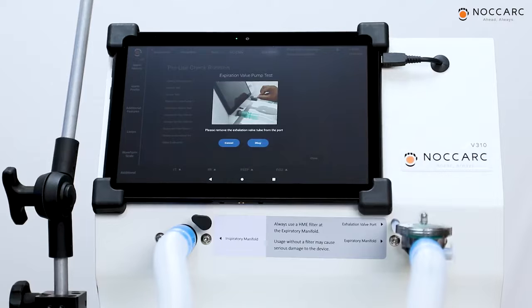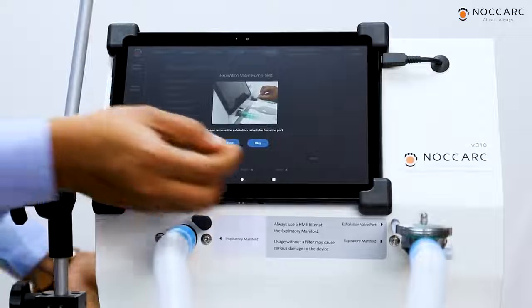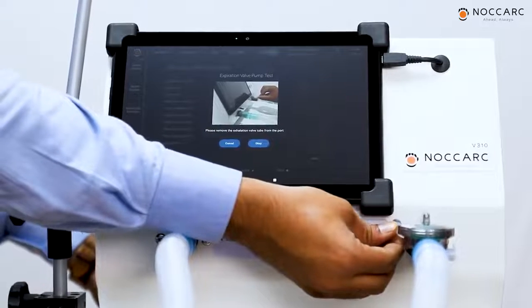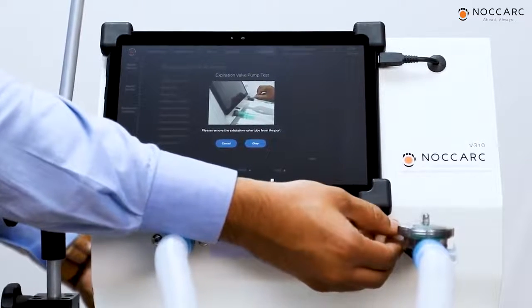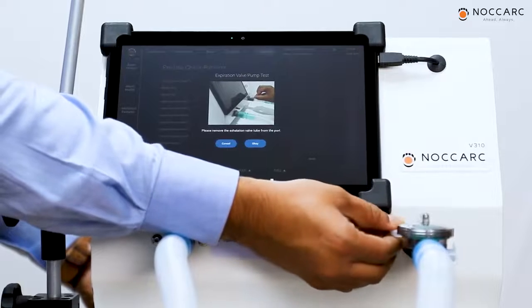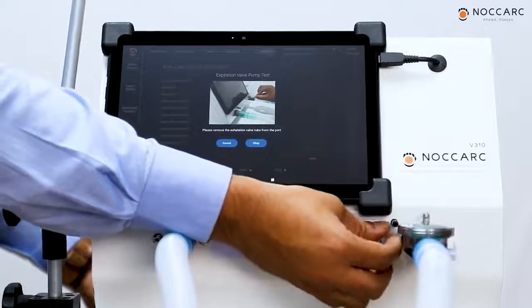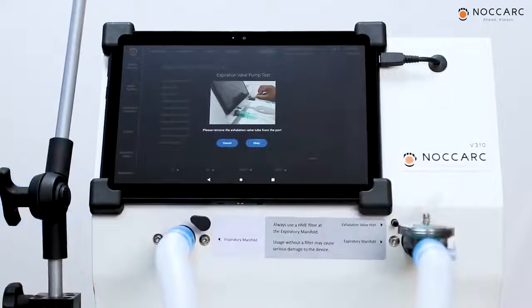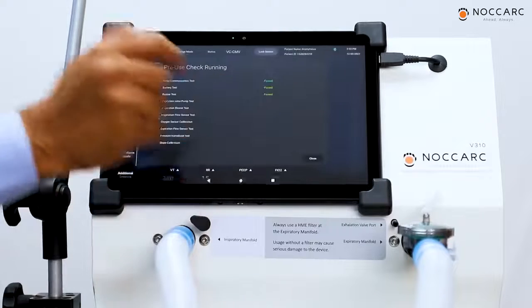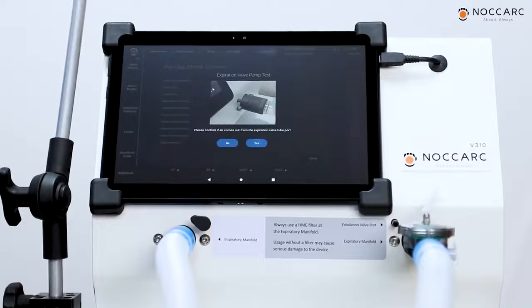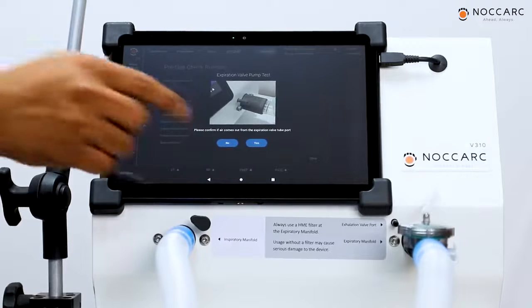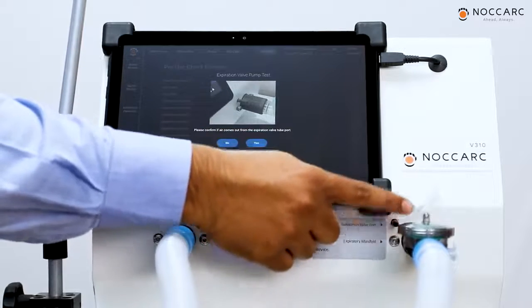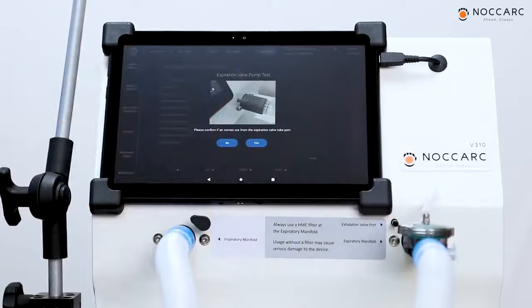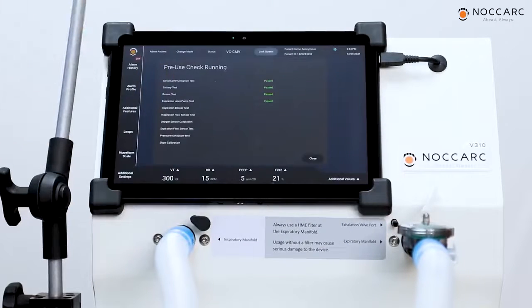Next is please remove the exhalation valve tube from the port. So this is your exhalation valve tube port. So I will remove this tube from this port. Then I will press OK. Please confirm if air comes out from the expiration valve tube port. So I can feel there is air coming out of this port. So I will press yes.